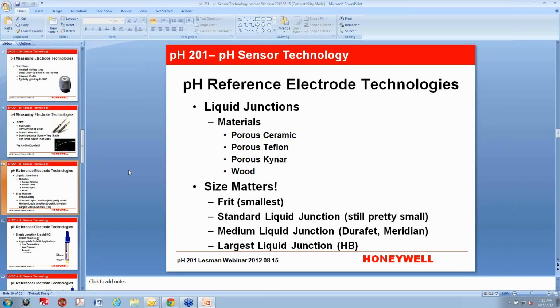And with the liquid junctions, the size of those holes or the pores is very, very important, and the size of the junction itself. That's important because, yes, you want to keep electrical contact, but you don't want process fluid to go into the reference area and mix with the potassium chloride in there, because it changes the voltage potential around the reference electrode, and that causes an offset in your sensor, and you'll see it as drift in your measurement. You keep calibrating down, down, but the sensor keeps going up, up, and that's a drift problem.